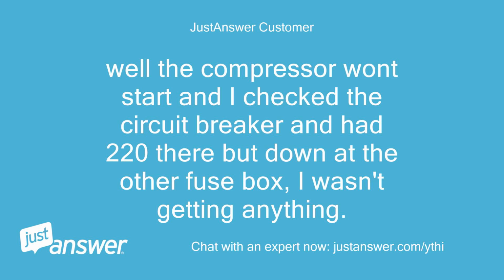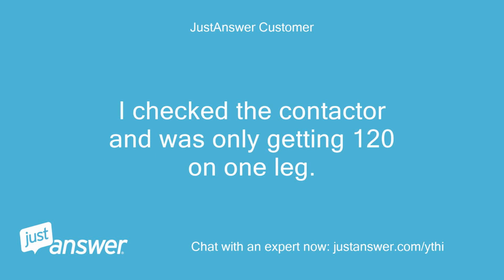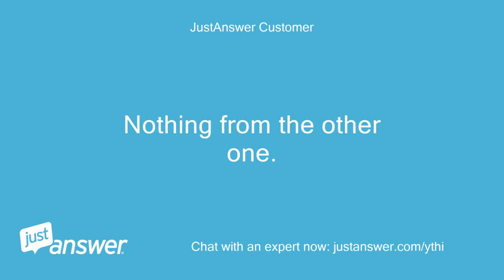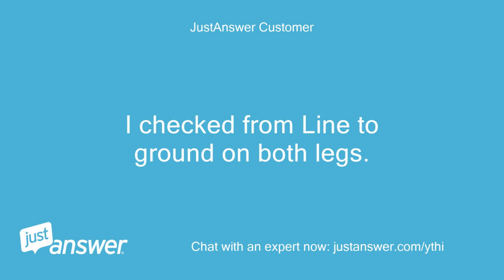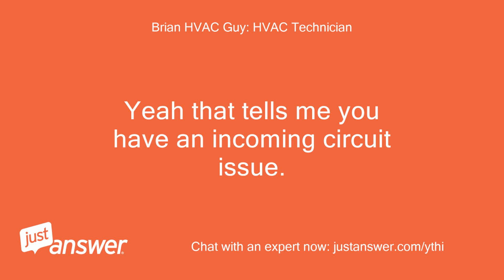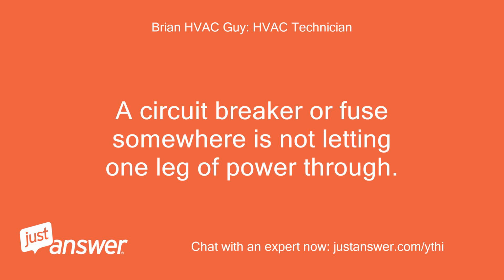Well, the compressor won't start and I checked the circuit breaker. It had 220 there, but down at the other fuse box, I wasn't getting anything. I checked the contactor and was only getting 120 on one leg. Nothing from the other one. I checked from line to ground on both legs. Yeah, that tells me you have an incoming circuit issue. A circuit breaker or fuse somewhere is not letting one leg of power through.